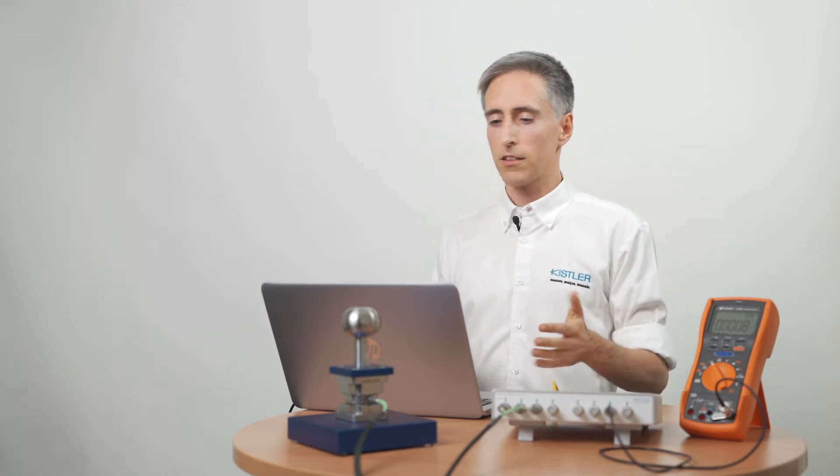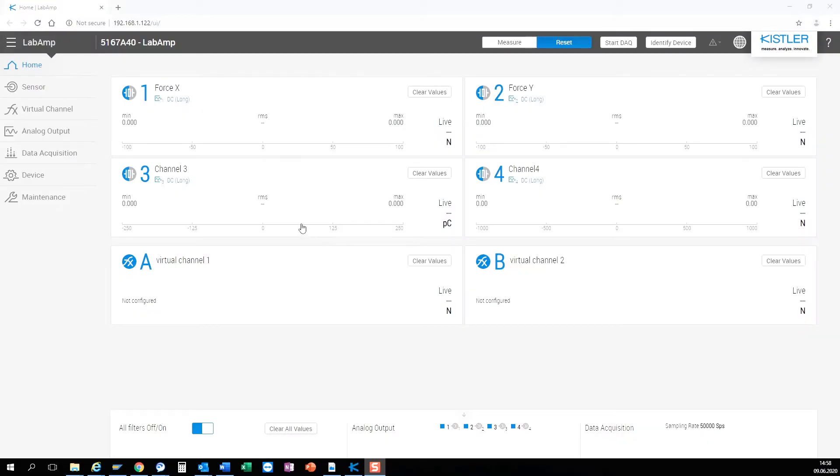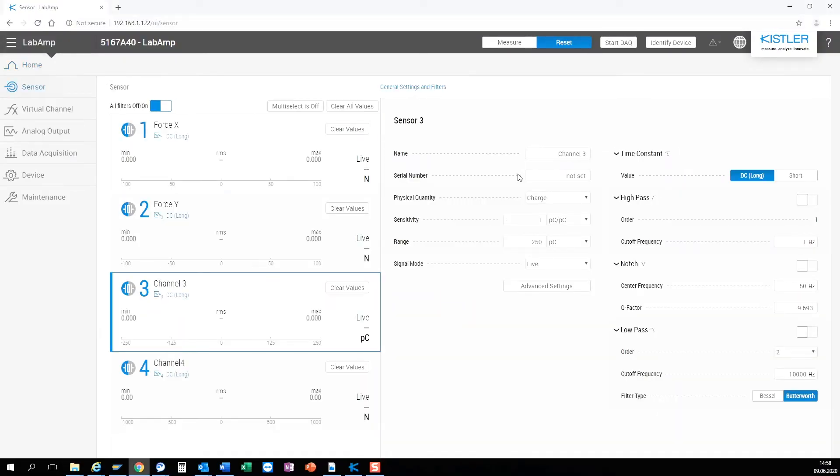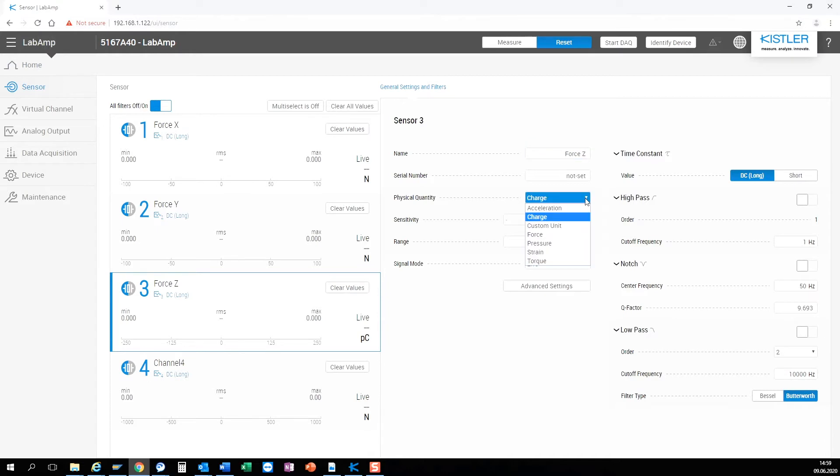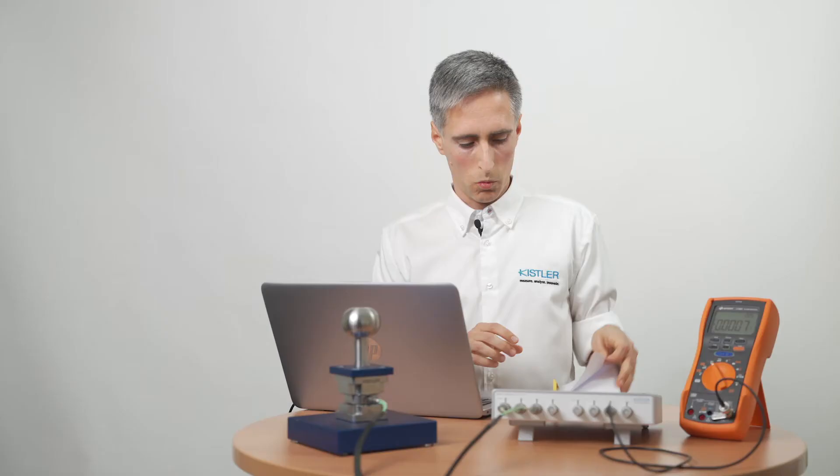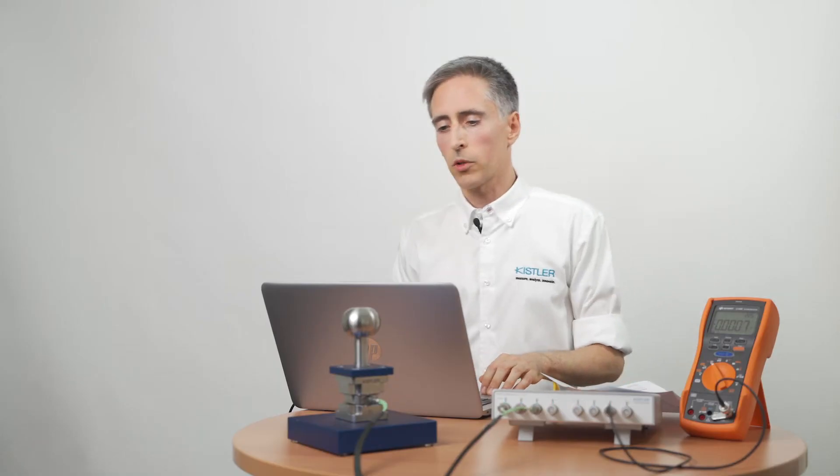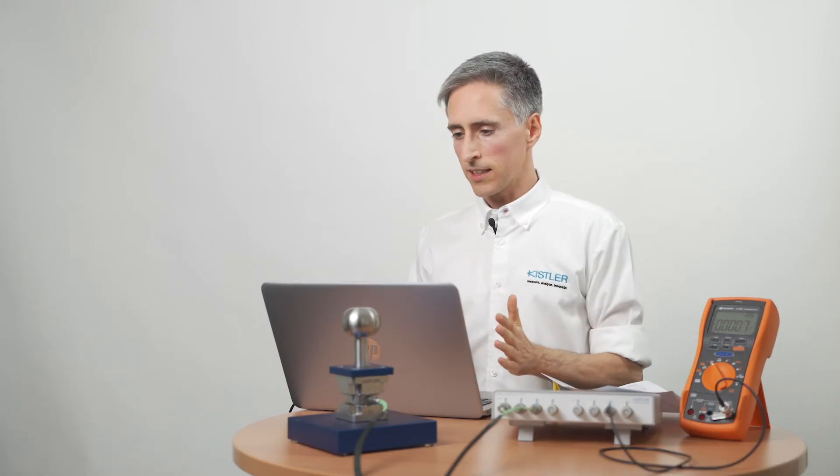All I need to do now is configure the sensor inputs correctly and if needed the analog outputs. Since the device also provides some integrated data acquisition we can also easily capture some signal. I click on a channel, give it a name, select the physical quantity, and enter the sensitivity of the sensor which I find in my calibration sheet. And I select the measuring range where I expect my signal to be.